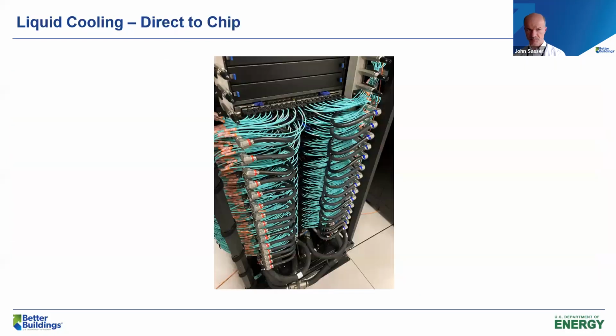This is direct chip liquid cooling. So this is a little different. You see the tubes going into the servers. Those actually go to a cold plate right next to a CPU, and about 70 to 80% of the heat is rejected via the liquid, with about 20% still rejected via air.